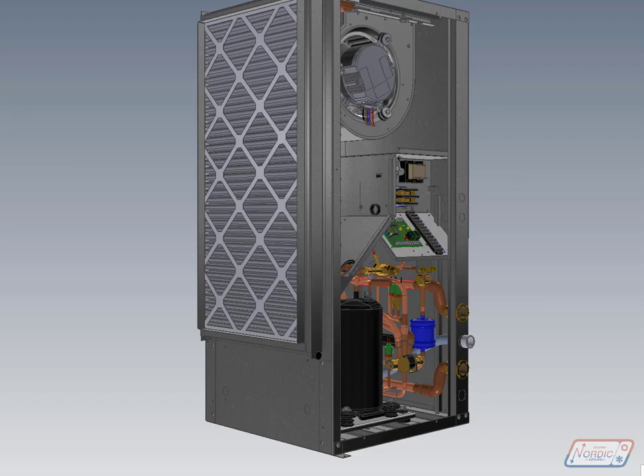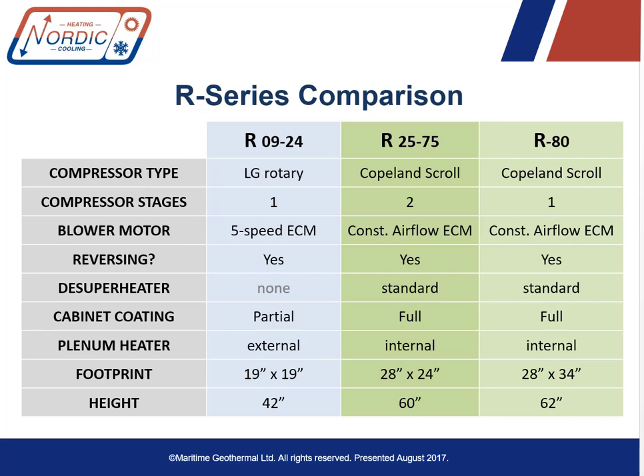Okay, so I've mentioned several differences between these commercial R units and the residential ones, and these can be summarized in a chart, so you can easily see the difference between them. The compressor, as I mentioned, is an LG rotary rather than a Copeland scroll. There's one stage of compressor operation. We have a 5-speed ECM instead of a constant airflow ECM. The unit is, of course, reversing in all cases for heating and cooling. We don't have a desuperheater for domestic hot water on the commercial series. The cabinet is partially powder coated, the doors.